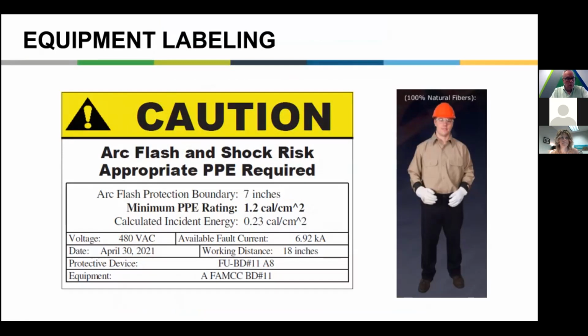Okay, so equipment labeling goes from the lowest levels of arc flash energy that is calculated to the highest levels. The bottom level is if the calories are less than 1.2. So this is an example label that we currently use for one of our clients. And basically, if the calories are low enough, a face shield is not necessary. A full body arc flash suit is not necessary. Basically, long pants, long shirt sleeves, non-melting natural fiber, and protection for your hands.